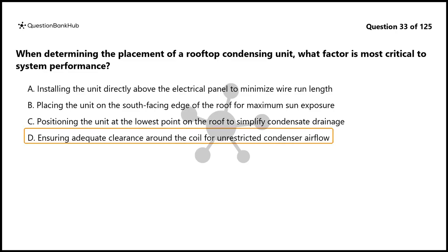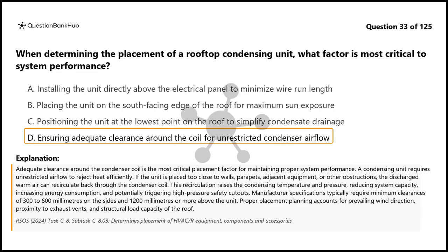The correct answer is D. Adequate clearance around the condenser coil is the most critical placement factor for maintaining proper system performance. A condensing unit requires unrestricted airflow to reject heat efficiently. If the unit is placed too close to walls, parapets, adjacent equipment, or other obstructions, the discharged warm air can recirculate back through the condenser coil. This recirculation raises the condensing temperature and pressure, reducing system capacity, increasing energy consumption, and potentially triggering high-pressure safety cutouts.